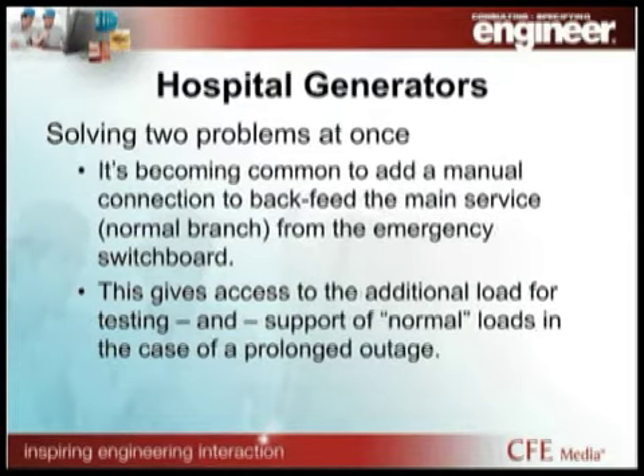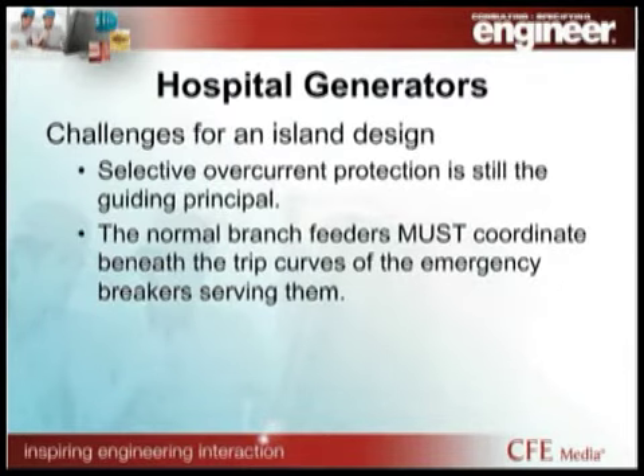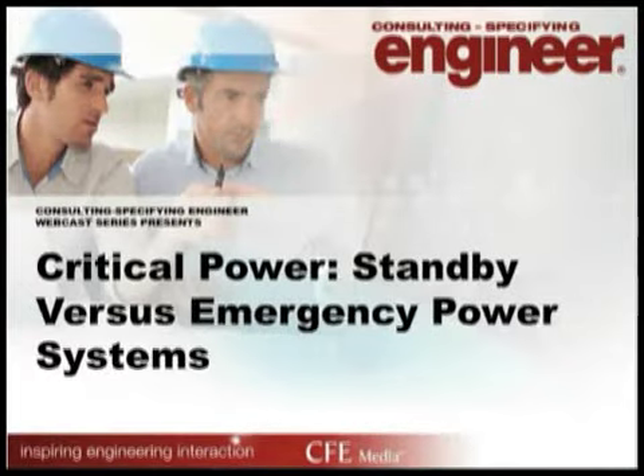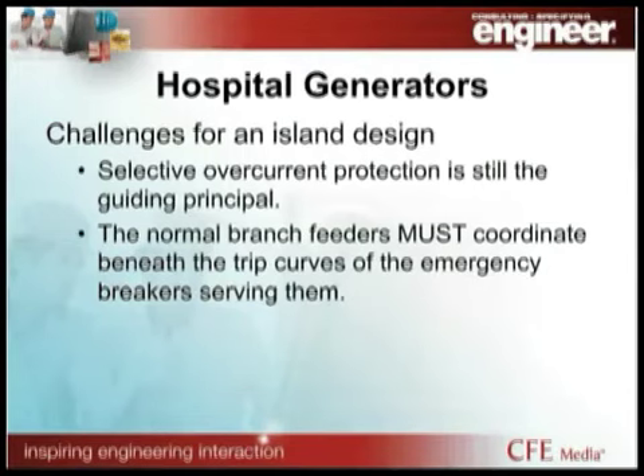There is a little bit of a hook on that. Two problems, challenges. One is when you've added the manual connection to backfeed a main service or a normal branch from the emergency switchboard, you also still have to maintain that overcurrent protection coordination. So whatever sizing criteria you used for your generator breakers on your emergency side, you now need to follow on the normal side, so that the coordination study is able to function correctly. You can't have a breaker larger on the normal side than you would have. So with that, I'm going to go ahead and pass the presentation over to my partner, Dwayne.